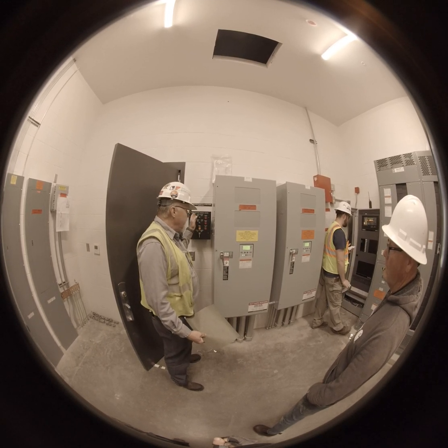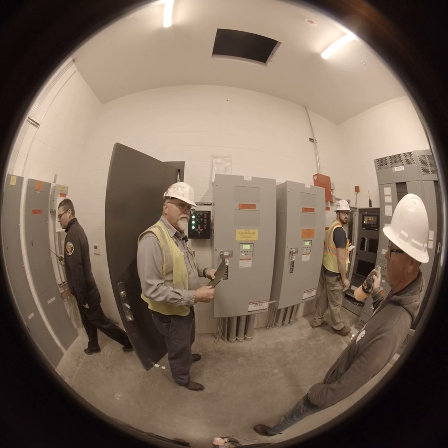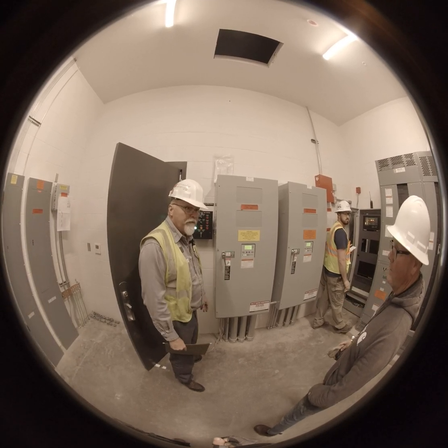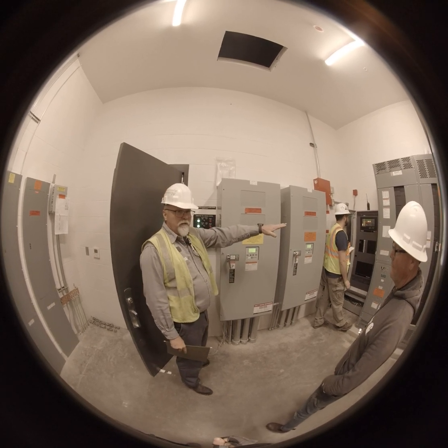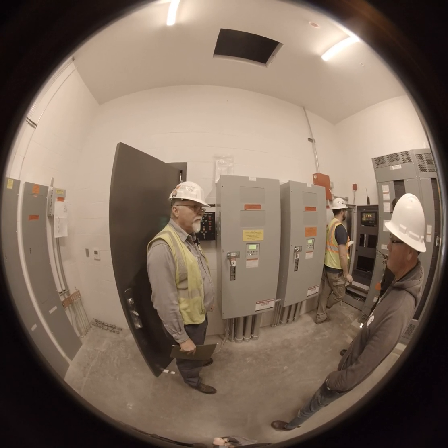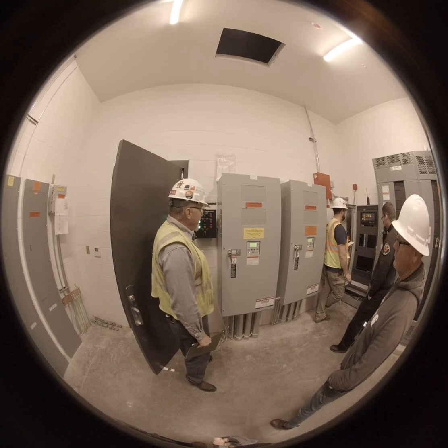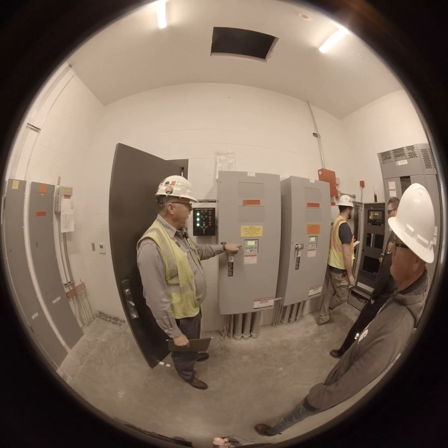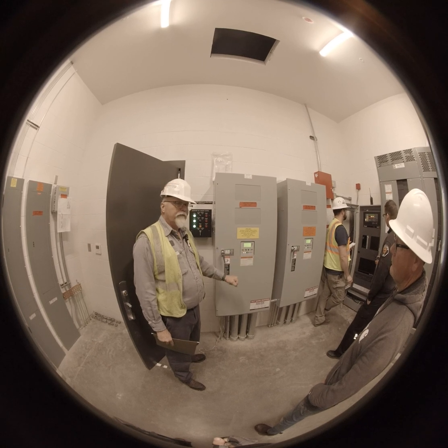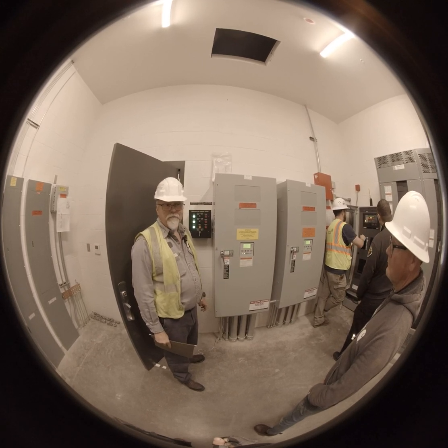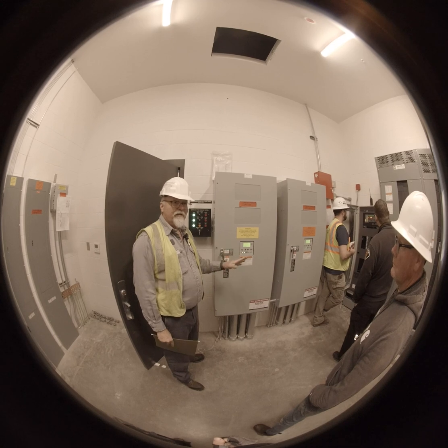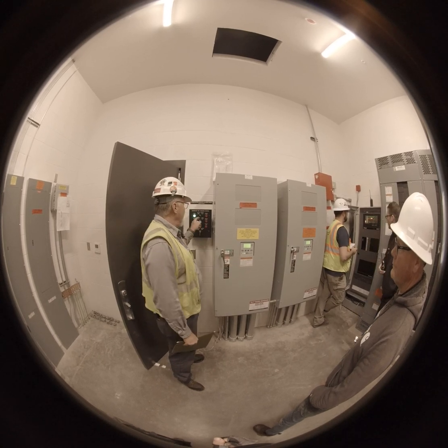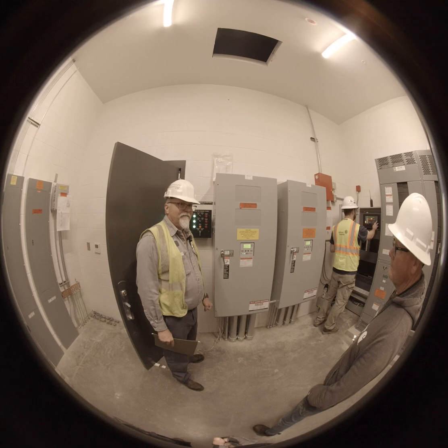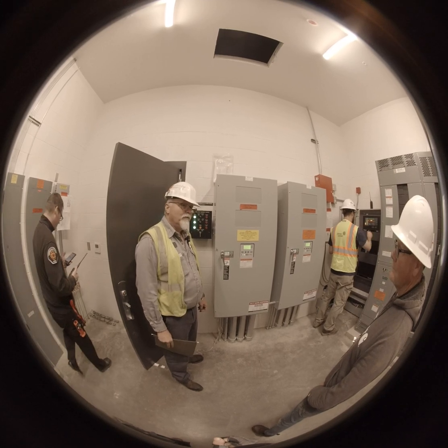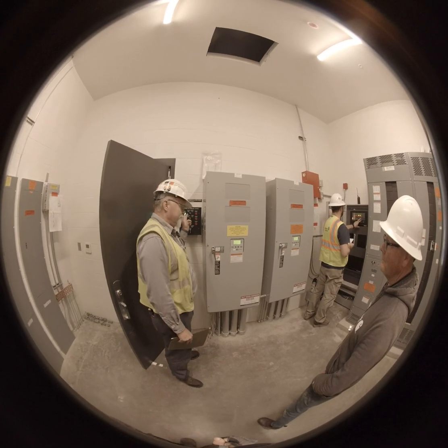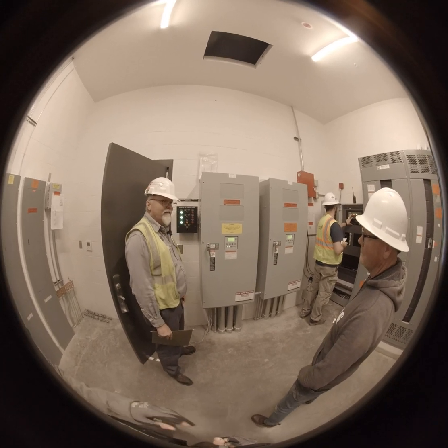When it transfers, the alarm doesn't know, right? Anytime they're seeing when that generator runs. But the only difference between this and this is, in here, you go in there and you transfer it over, and then you can walk away, because five minutes later, it's going back. If you use this one, don't walk away, because you're going to have a hefty fuel bill. It's going to stay running until something else shuts it down.